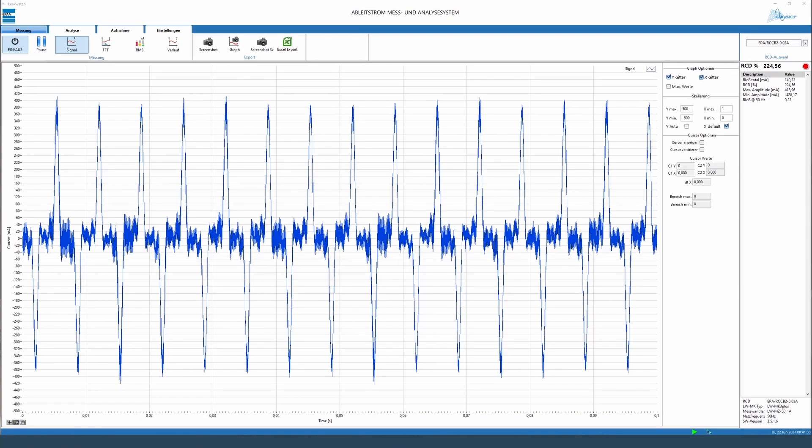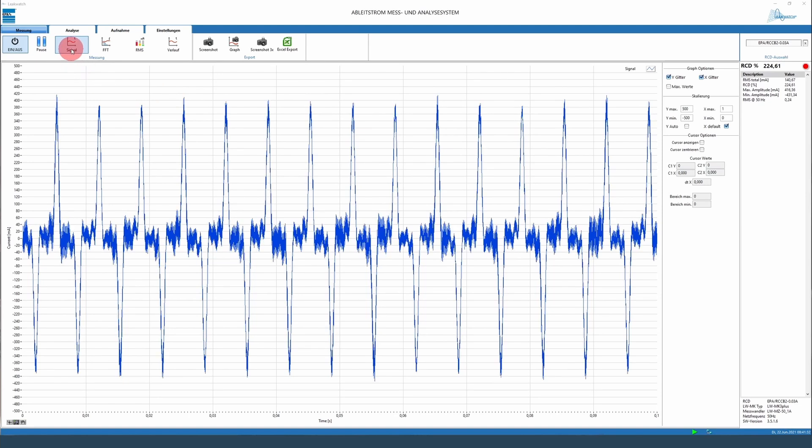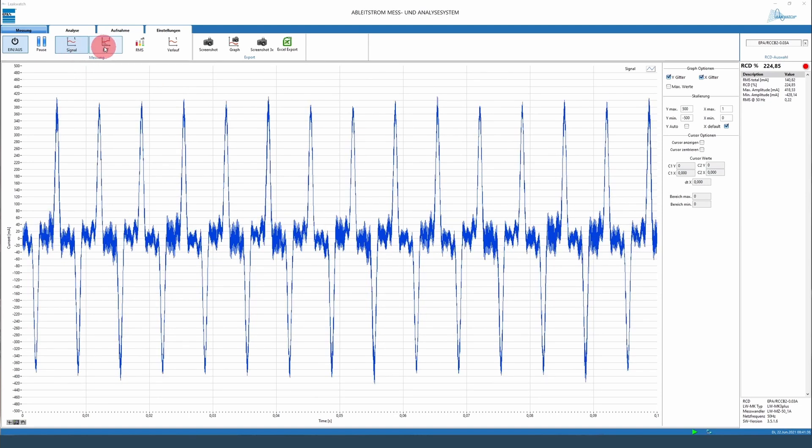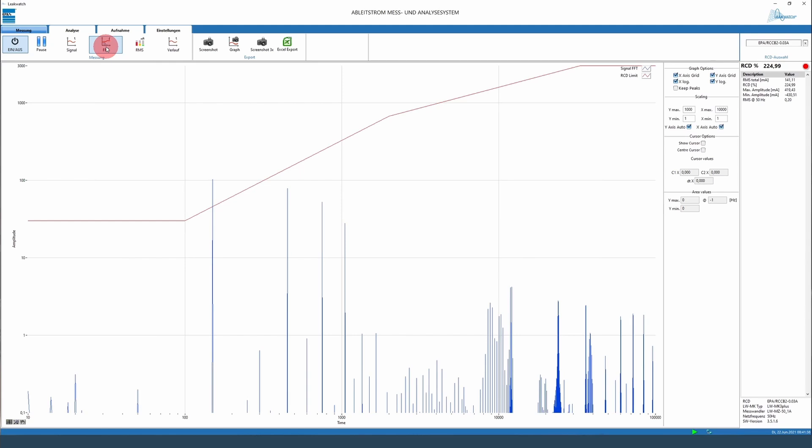The LWsoft can be used to display the current measuring signal or via the FFT tab the individual frequency components of the measured value as well as the load factor of the upstream RCCB. Tripping curves for all common RCCB models of different manufacturers are implemented in the software and can be selected via a dropdown menu.